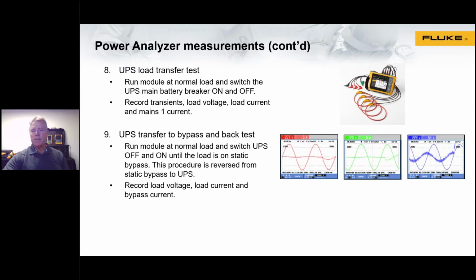For combined testing, what you would do at this point is remove your load banks, connect your critical loads as well as the standby generator system, and repeat the same tests at 0% and 100% load conditions. We would want to be looking for transfer between the main supply, UPS, and standby generator to ensure that transients and waveform distortion stay within acceptable limits.